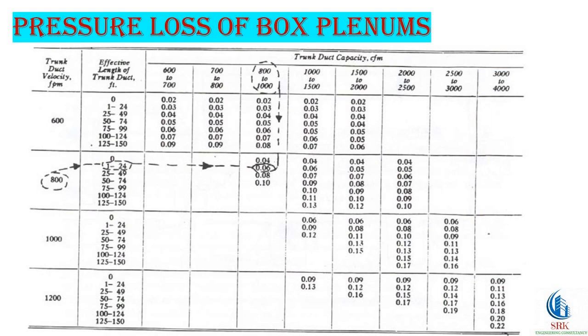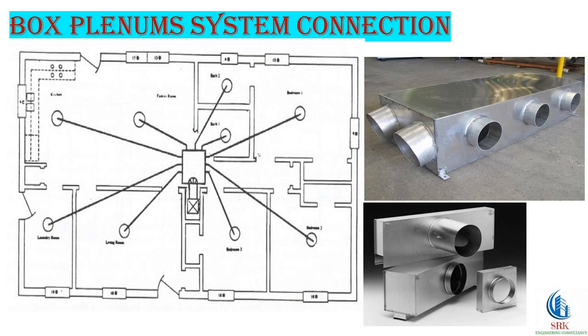Any supply trunk duct between the conditioning unit and box plenum is sized based on the supply system CFM and an acceptable air velocity of from 700 to 900 feet per minute, FPM. The relationship, duct area equals CFM divided by air velocity, is used to determine trunk area, or entrance opening area if no supply trunk is required. The effective length of the supply trunk, if one is used, is determined based on the measured length of the trunk and the equivalent length of any fittings used in the supply trunk.